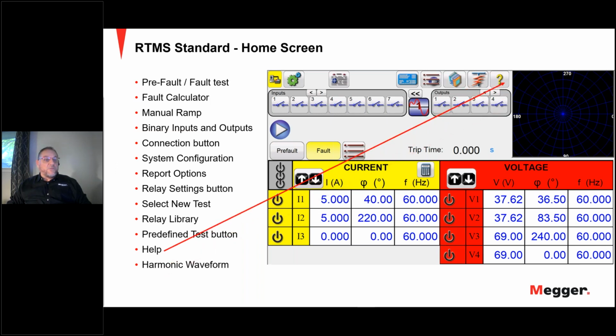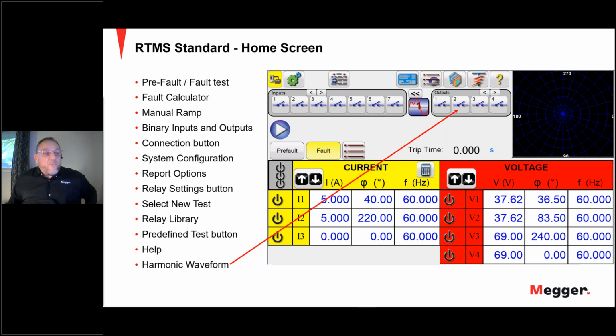The help button will provide help for both software and hardware, including a hardware system reset. And then lastly on this screen is the harmonic waveform, where users can define up to 4 waveforms. All 4 waveforms will be summed together to create a complex waveform from any or all of the selected outputs. If no value is entered for the second or third waveforms, then the output will simply be the fundamental default frequency sine wave. So it's a very powerful tool which will not require any lead changes or any hardware changes. It will run on the fly.